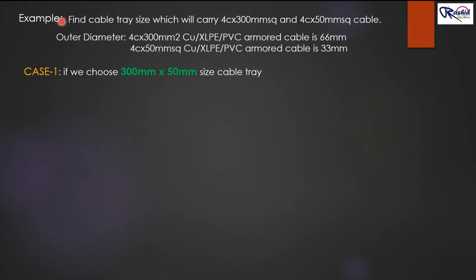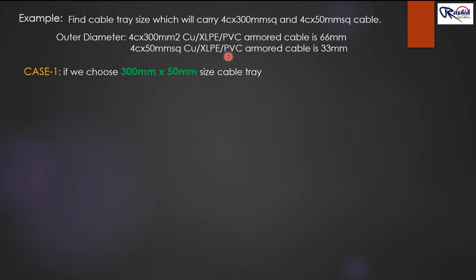Now let's see an example. Find the cable tray size which will carry: 4-core 300 mm² copper XLPE PVC armored cable with outer diameter 66 mm, and 4-core 50 mm² armored cable with outer diameter 33 mm.